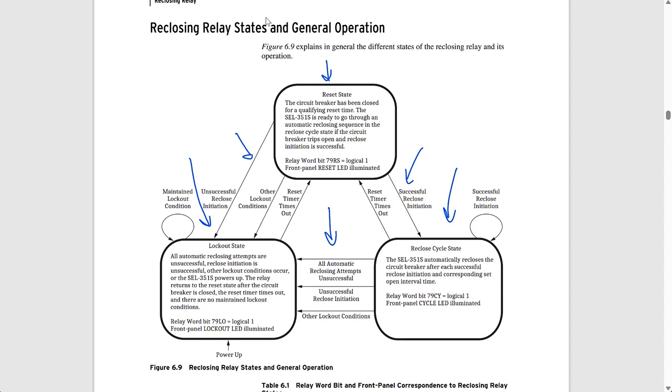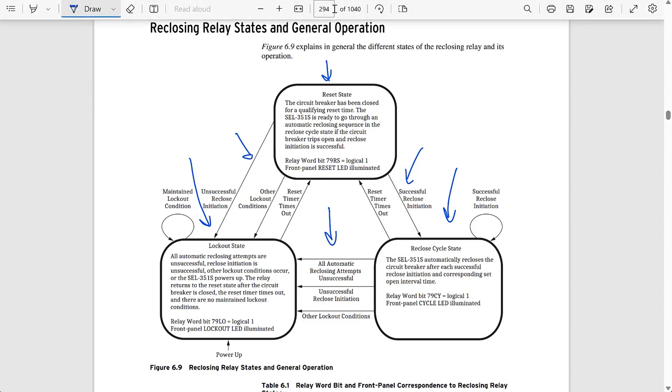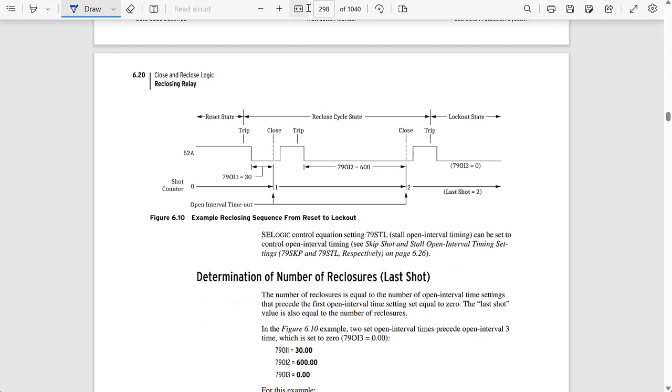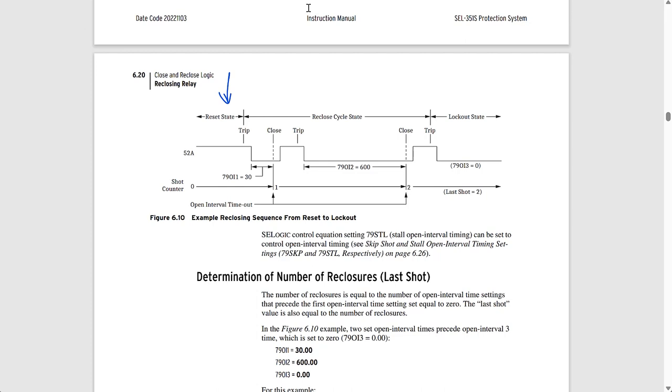Let's look at another figure in the instruction manual on page 298 that shows an example of how the sequence operates. This example has two shots — remember that a shot means an automatic reclosure by the relay. We start from the reset state with the breaker closed, as indicated by the 52A relay bit being picked up. Then we get the first trip, which is what we call the reclose initiate.